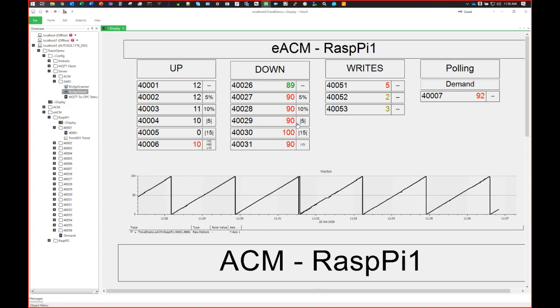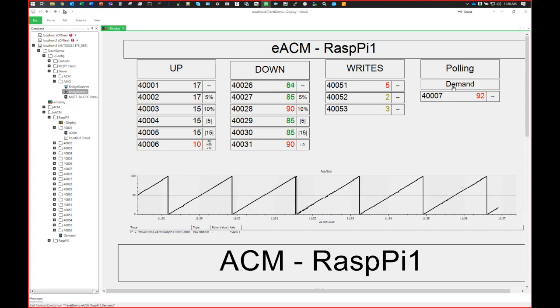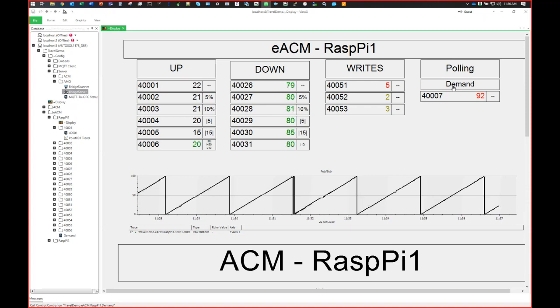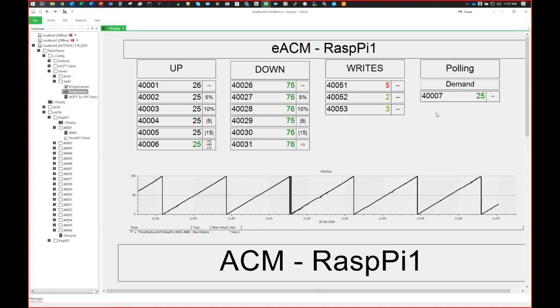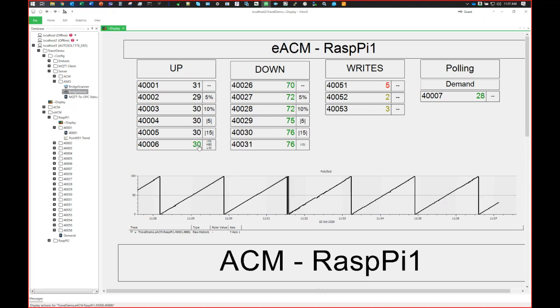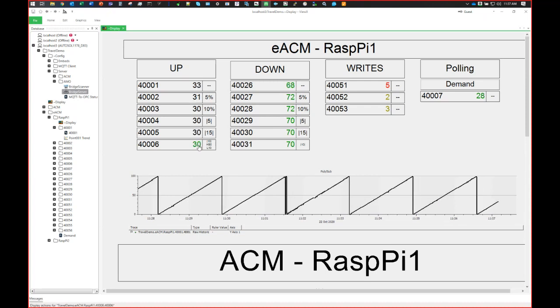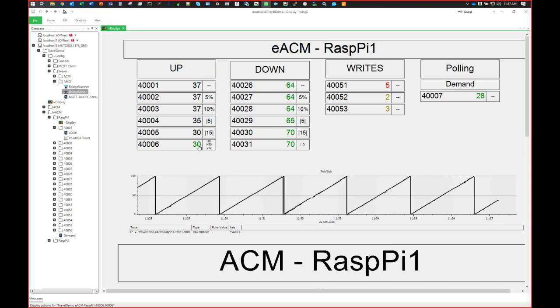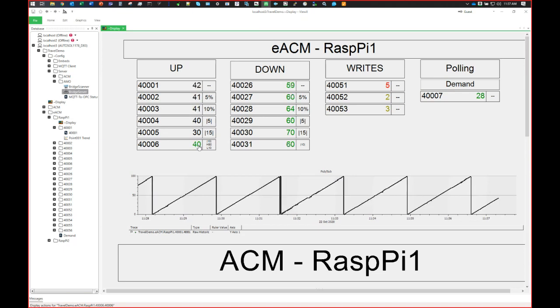And something I would also like to point out is if I do a demand, well, let me wait until it cycles to 20 real fast because I'll need 10 full seconds to talk. There we go. If I hit a demand, you'll notice that I'm actually going to update this tag as well as this tag, but he'll still update at 30. This is an out of band gathering of data. So all of your dead bands will still be there. Again, this is just so that way your operator feels good about this deployed technology. He still feels in control because he is.